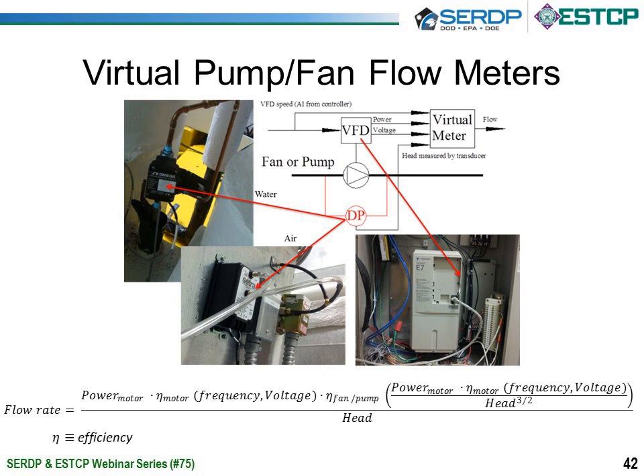The other type of virtual meter we have is a virtual pump or fan flow meter. The diagram for this, if you'll focus in on that, takes a VFD speed signal or frequency signal that comes from the controller that goes into the VFD, so the VFD responds by providing the corresponding frequency. We also have power measurements and voltage measurements coming out of that. Those two measurements, along with the VFD speed command, go to the virtual meter. In addition, we also measure the pressure difference across the fan or the pump, indicated by the red DP and the lines coming off of the pipe or the duct in which the fan or pump are located. That measurement is also taken and input into the virtual meter.